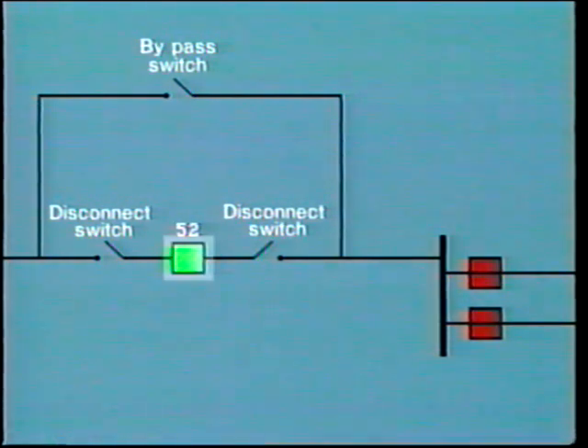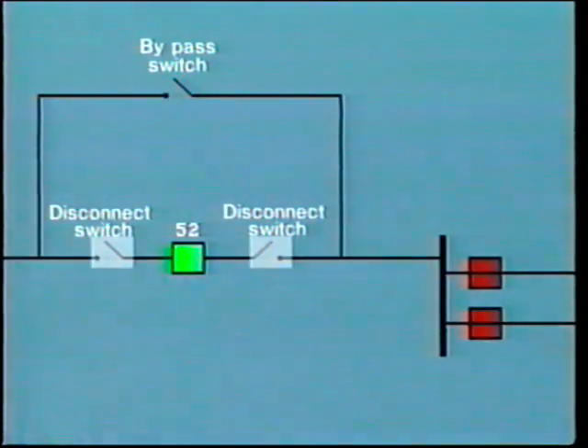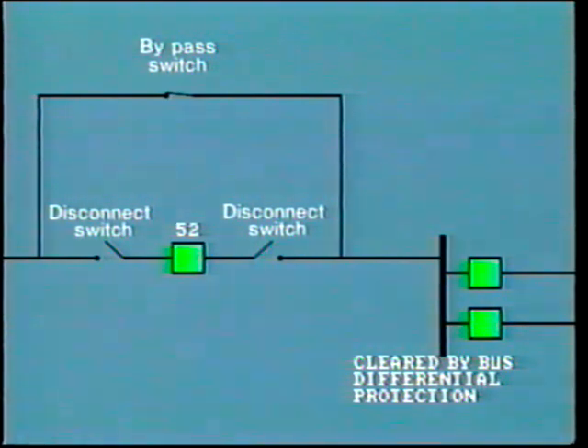This breaker number 52 was under maintenance by electricians. The two disconnects on either side were open, and the bypass switch was also open. One of the electricians out in the yard called and asked the relay technician, who was working on the control house panel, to try and close the breaker for the maintenance crew. Remember, it was isolated. In fact, the technician got hold of the wrong handle and closed the bypass switch instead. At the instant of contact, the bus differential protection operated and cleared the whole bus.